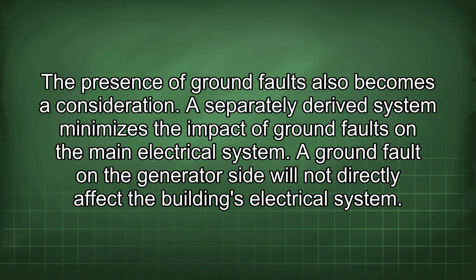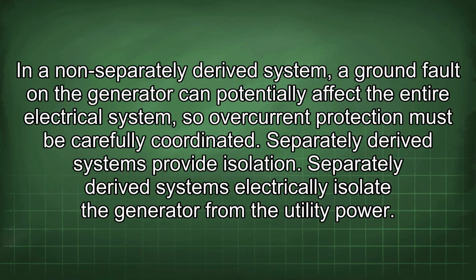A separately derived system minimizes the impact of ground faults on the main electrical system. A ground fault on the generator side will not directly affect the building's electrical system. In a non-separately derived system, a ground fault on the generator can potentially affect the entire electrical system, so overcurrent protection must be carefully coordinated.